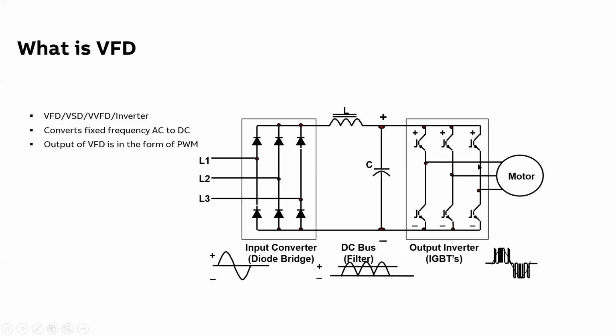Now this DC current is fed to the third part, which is the inverter section. This is made up of IGBTs. These IGBTs have their own switching pattern and a very high switching frequency, and based on the requirement and how it has been programmed, they switch, and then this DC current is converted into PWM output. So the output of a VFD is a pulse width modulated output. Actually, it is not a sinusoidal or analog signal, but a digital signal. However, because it's pulse width modulated, the width of the pulse keeps varying, and it resembles a sine wave. So although the output is not a sine wave, it resembles one, and then this output is fed to the motor.